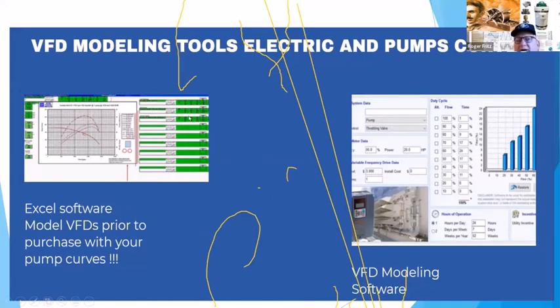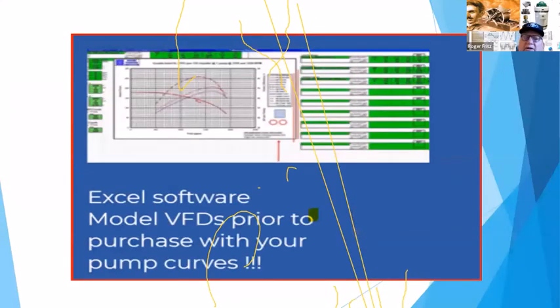Definitely in irrigation. He's shown many times how you can save 20% by just getting the pumps trimmed properly, getting the speeds operating to the correct points, and then just using a soft starter, which has zero losses on the input, and just start the motor slowly. One other point I want to bring up on starting is, a VFD normally has 2 or 3 set points that you can start the motor at, so you can accelerate it up to a point of pumping.